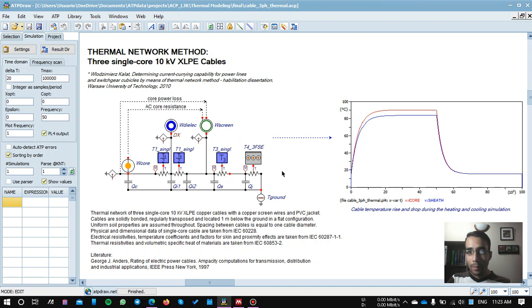We are sharing models blocks from a custom library to do the thermal network modeling and the transient response on the cables. So for a given size of the conductor, we are representing the electrical equivalent of the thermal network, right? So we have to represent thermal resistivities and thermal insulation of all the layers.